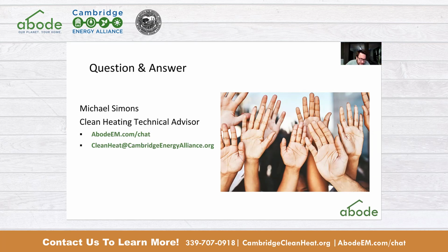With dehumidification, that one's easier to talk about. Any heat pump will have a mode button, and then it's heat, cool, or dry. In dry mode, it keeps the coils really cold, then slowly moves air over the coils, wicking away all the moisture in the air and dumping it outside. It works like you'd think a $5,000 dehumidifier would, extremely well. In summertime, half the reason we're uncomfortable in our homes is the air temperature, and the other half is the latent energy. So it pulls that out too, and it works really well.